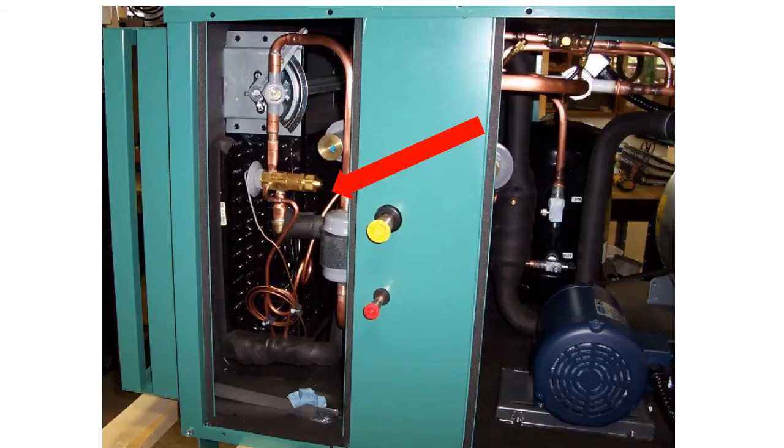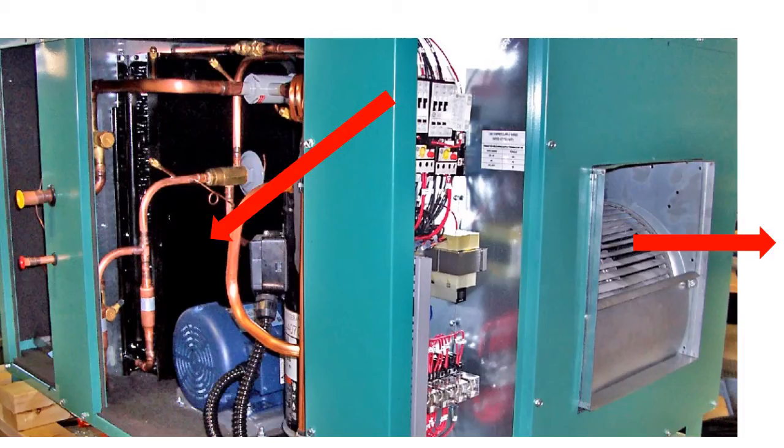Air enters the dehumidifier where it first passes through the evaporator coil, which drops the temperature of the air below the dew point before it passes through the reheat or condensing coil. After passing through the reheat coil, the air leaves the dehumidifier both warmer and drier than it entered, as in a conventional basement dehumidifier.